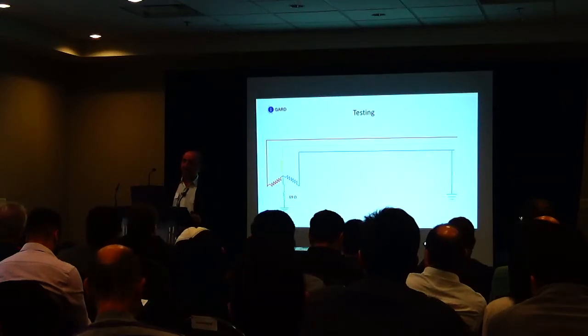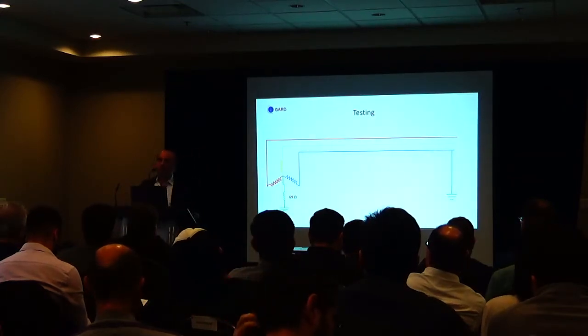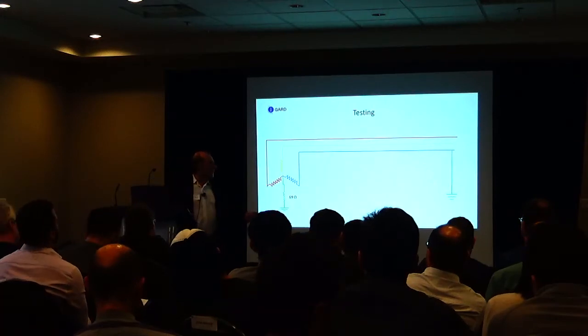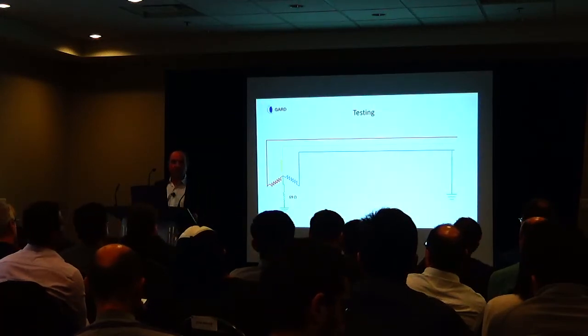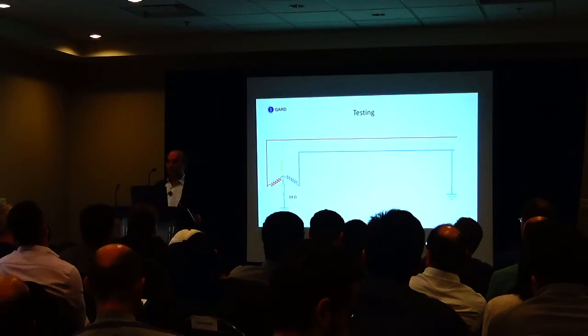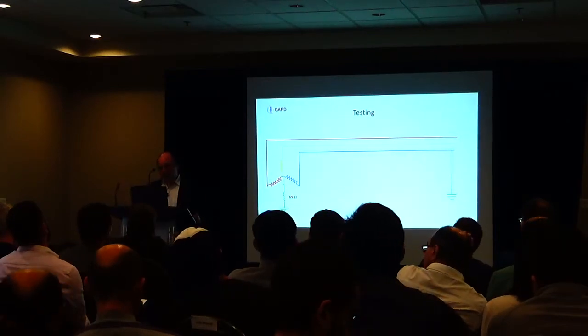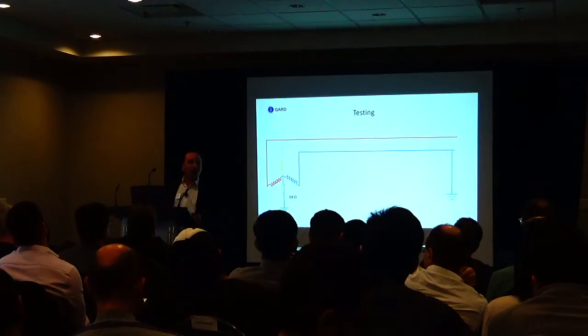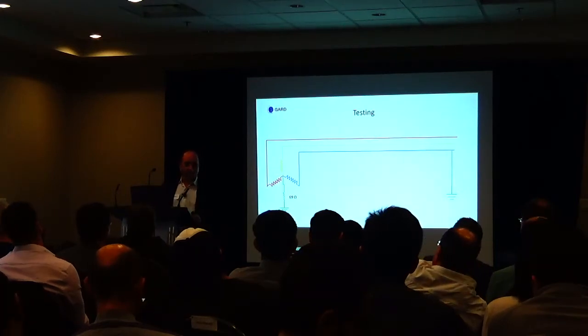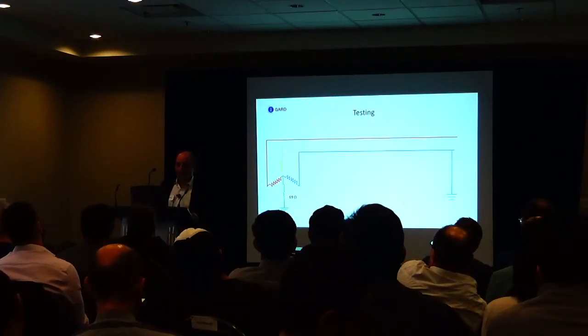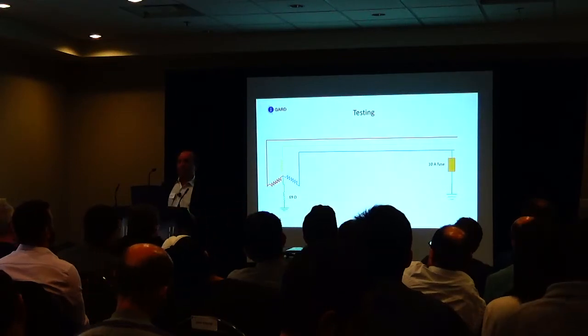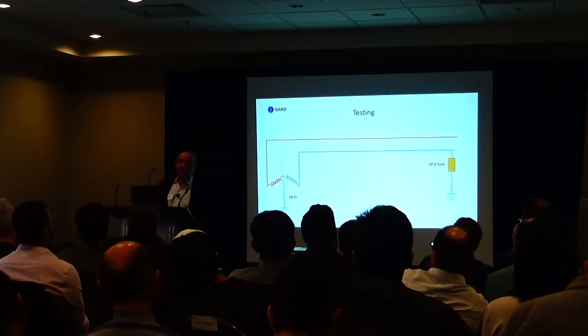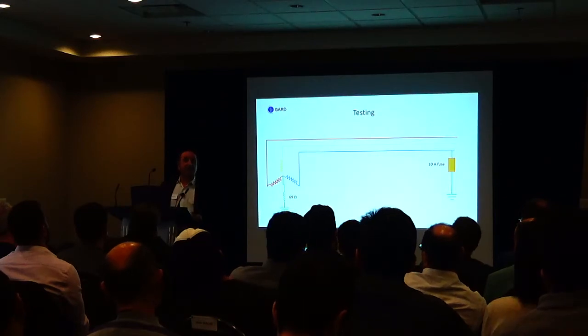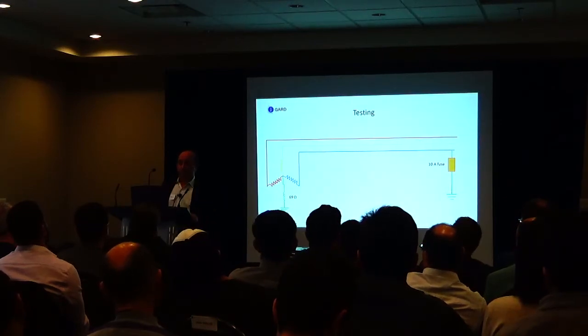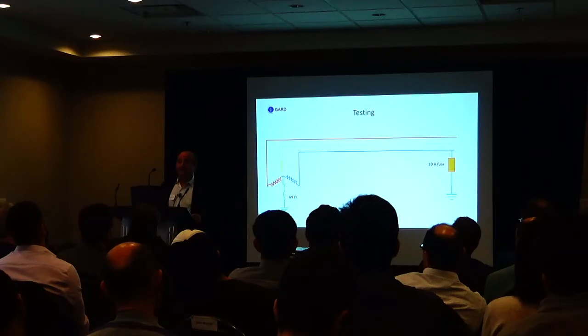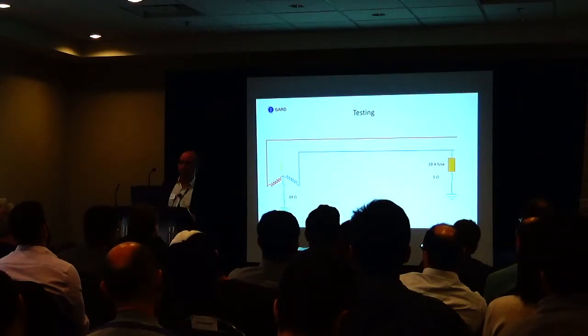Right? So we try to connect as much of the load as possible and put a fault on the system. Now, not many electricians like to connect a wire to C phase, the other end to ground, and turn on a switch. In fact, they look at you like you've got 4 eyes when you ask them to do this. And you can see why, right? So we can put a 10 amp fuse in there. If we put a 10 amp fuse in there, it should be okay. If there's a problem, the 10 amp fuse will blow. If that happens, we put a resistor in there as well.